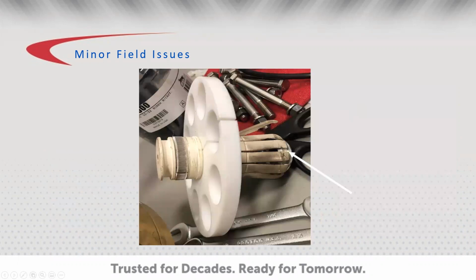The arrow in this photo shows the nose guard protector of the contact fingers, designed to facilitate installation and reduce the likelihood of split connectors. It was not intact during the time of installation, so it didn't do its main purpose, to keep all those fingers inside the inner. In these instances, they seem kind of minor, but the things that could have been caused from these would have been way more catastrophic had they not been found. So it was lucky that they found these when they did, before the system saw power.